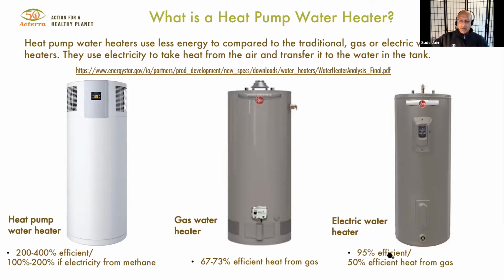So these are 95% efficient. But if you're getting your electricity from burning methane, then it's only 50% efficient if you take the actual heat of the gas. Compared to that, the gas water heater burns natural gas directly, so that's 67 to 73% efficient at extracting the heat from burning gas.